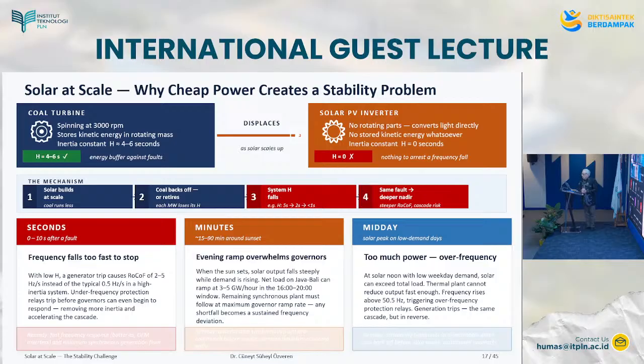So solar builds at scale, and coal runs less. When we increase our solar, even if we don't retire the plant, we'll have to back off and reduce the output of the coal-fired generator, or we can think about retiring it. And each megawatt we retire or reduce removes its H constant, the inertia of the system. Therefore, the system inertia falls, and for example, it can go from 5 seconds to 3 seconds to 2 seconds to 1 second, which means that it will be able to keep the frequency going for only 1 second, which is not long enough for the system to recover, unless there are fast-acting batteries and synchronous condensers in the system.